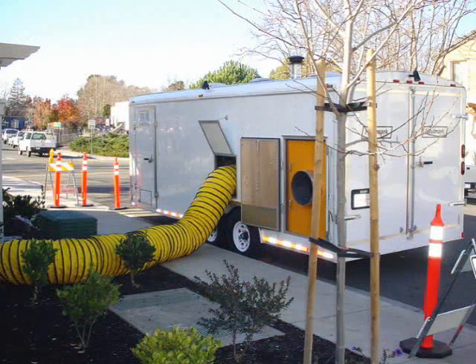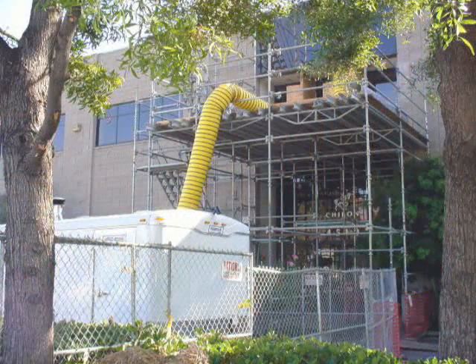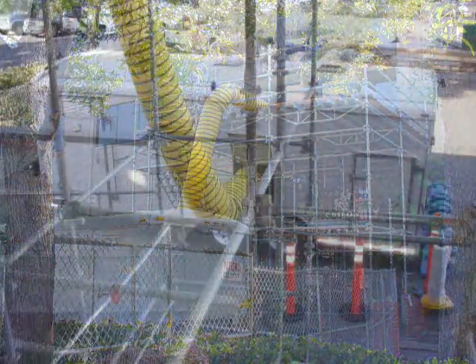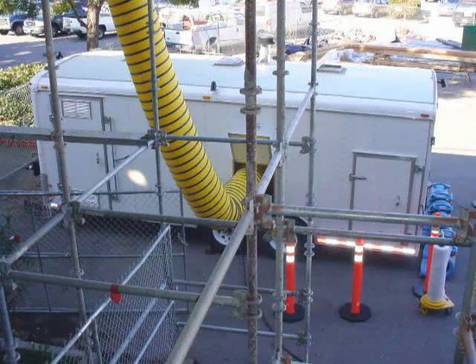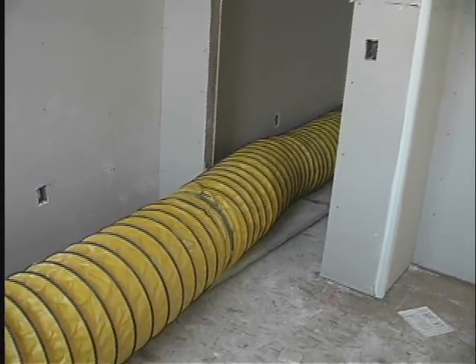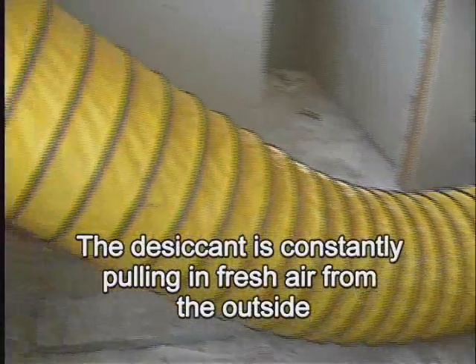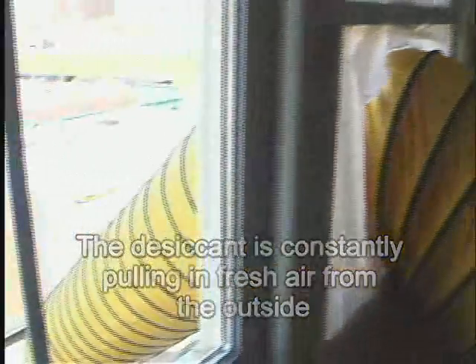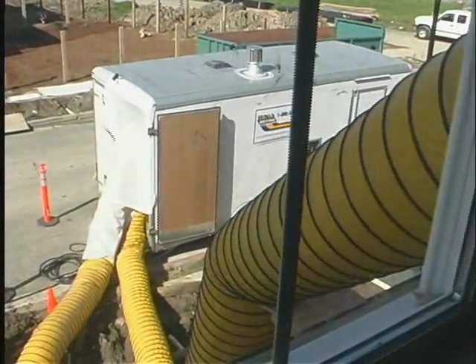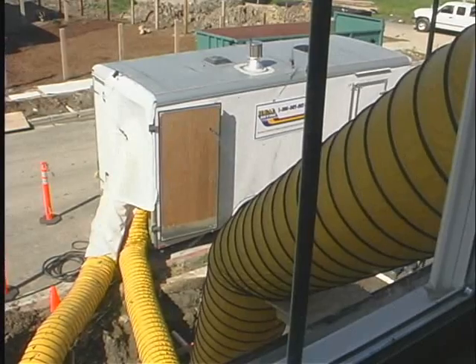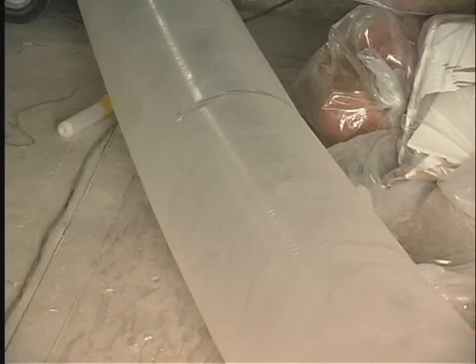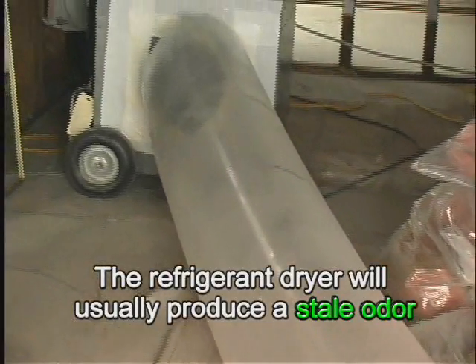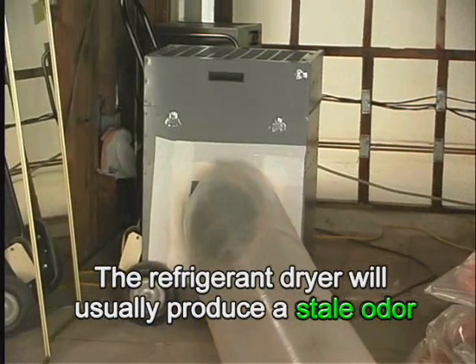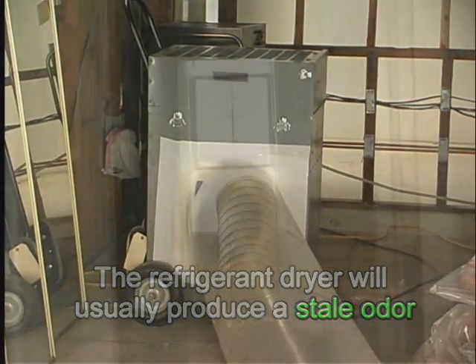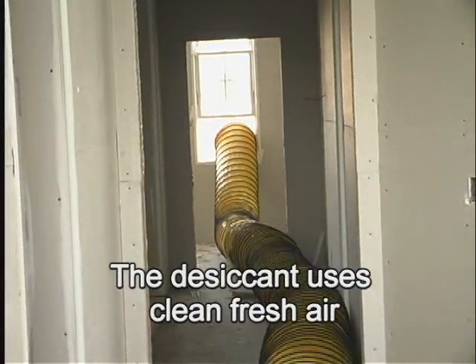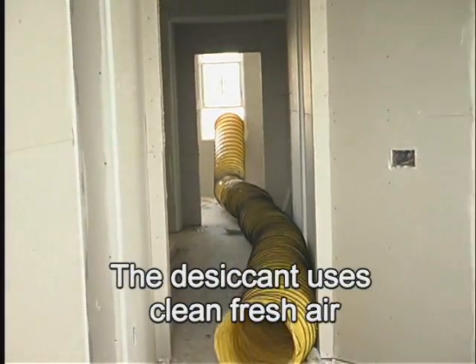With temperature variances in mind, the desiccant will usually dry faster in an overall rating when compared head-to-head with the refrigerant drying system. The other advantage is that the desiccant is constantly pulling in fresh air from the outside and therefore is not simply recirculating the possibly contaminated air inside over and over. The result is that the refrigerant dryer will usually produce a stale odor while operating within the containment field, while the desiccant, constantly using clean, fresh air, will produce no stale air.